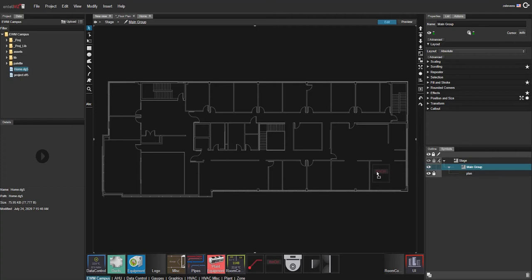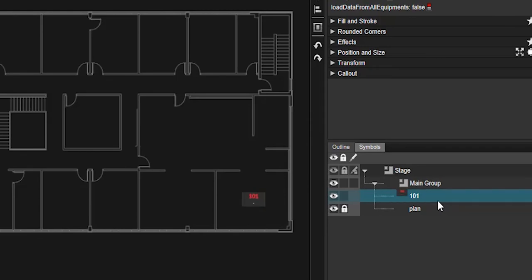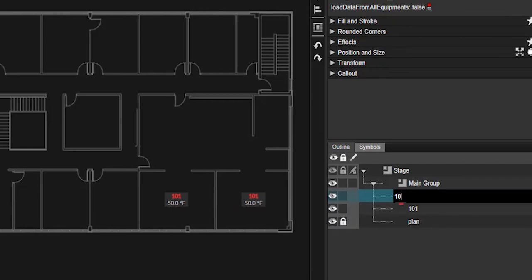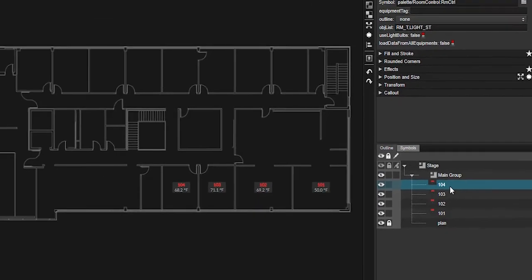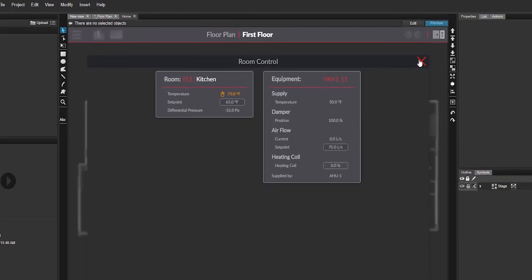Now to move on to creating graphics using pre-made symbols that tag spreadsheets. I've already introduced a few of the symbols available in the default project template. Let's take a look at a floor plan graphic. All you need to do is use the room control symbol on your floor plan and change its layer name to represent a room number — let's say room 101. It filters the spreadsheet and finds all relevant information pertaining to that room. It will show you room temperature by default on your floor plan, and when you click on it, it will open up more information about that room automatically as per the spreadsheet information. There are lots more examples like this available in training videos on our support site.